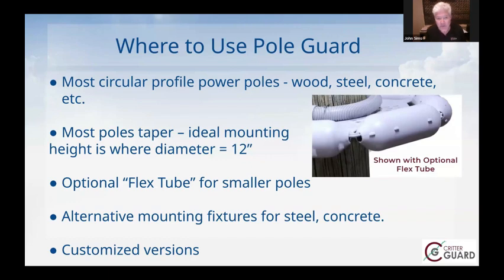Some other options we offer for pole guard: you see this flexible tube in the picture to the right. For poles that aren't quite large enough—since it's a molded plate that goes around a 12-inch opening—if the pole is maybe less than 10 inches, you'd have a gap of an inch or more all the way around, depending on the pole size. That might be enough for a snake, chipmunk, or other small critter to crawl through. That's what the flexible conduit is for—it's just a gap filler, a simple, easy way to adapt pole guard for multiple size poles.